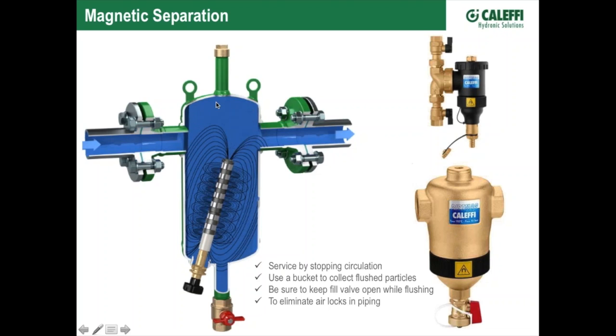Knowing that sometimes this dirt separator will be put on the return side of a piping circuit, maybe it's close to the bottom of the boiler, it might be close to the floor. How are you going to get a long magnet out of that? So we segmented the magnets here, so as you pull this out, you can actually tip these apart, and same thing when you put them back in. So they kind of bend, so to speak, so as you put this in there, the segments click together and you push it in there. So that's the way that we're able to get a very strong magnetic device up inside a steel vessel and do a good job.